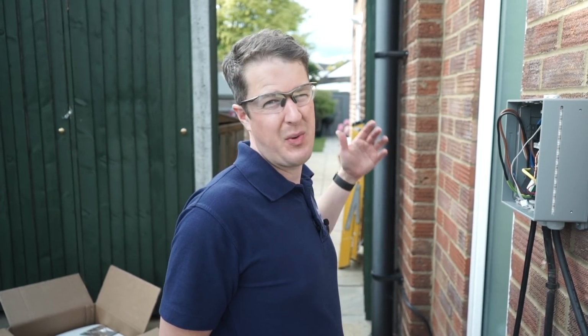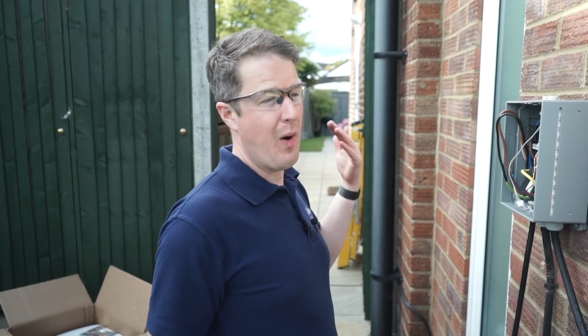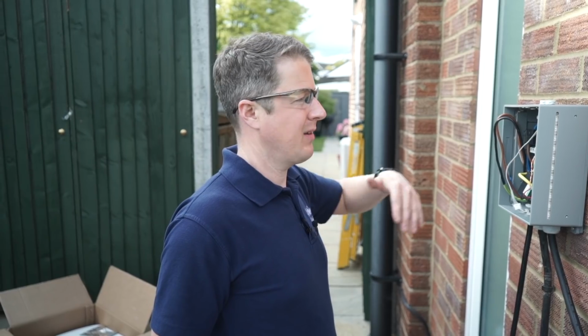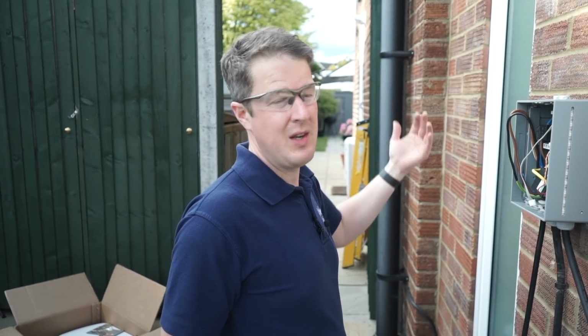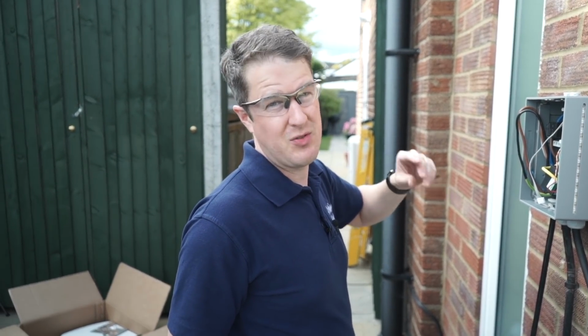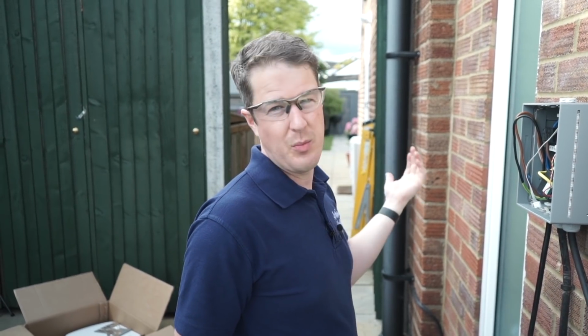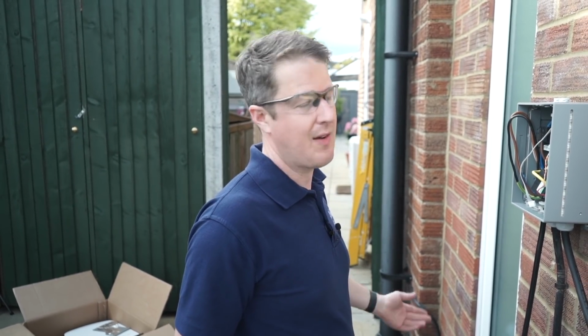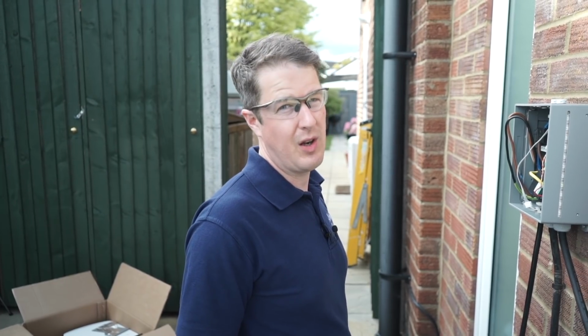Here it's 100 amps, so we can set a grid limit of 100 amps. What will happen is, if the power consumption of the whole house is say 90 amps, it will ramp the charge point down to 10 amps really quickly, so it stops it from blowing the main fuse. It's just a safety feature, but it's quite important if you've got a lot of loads in your house.